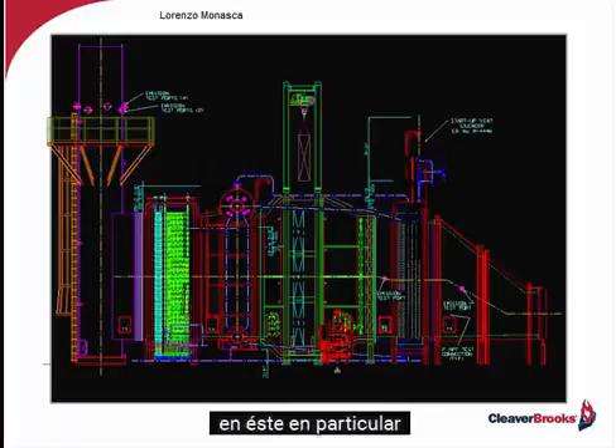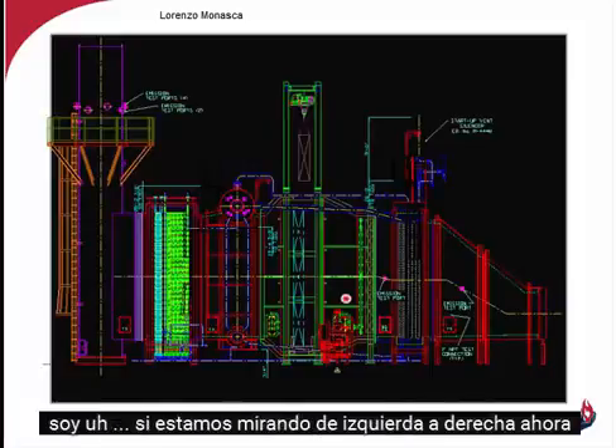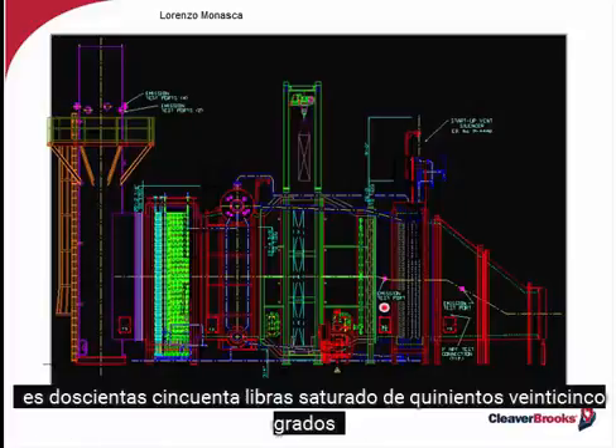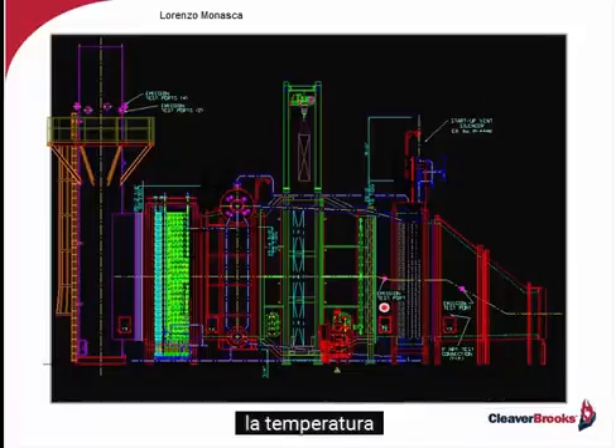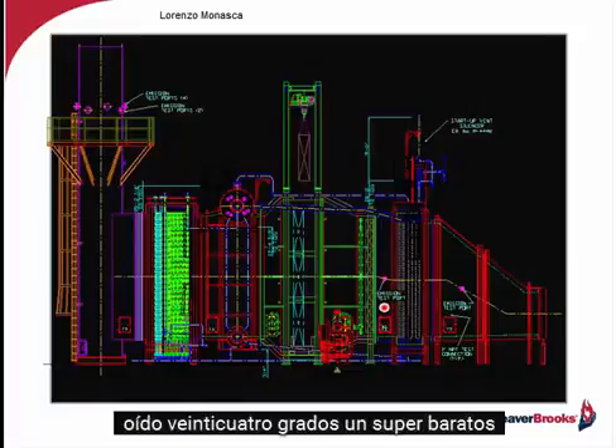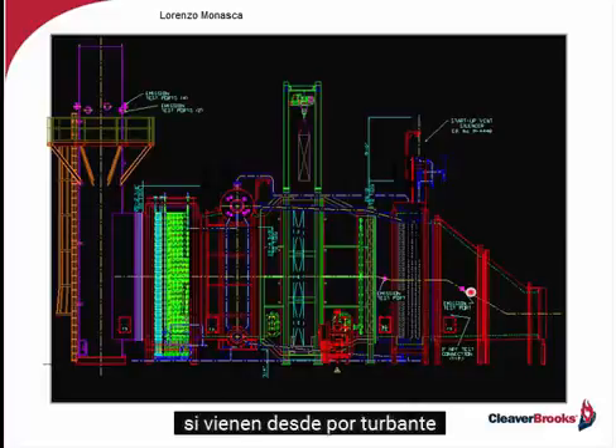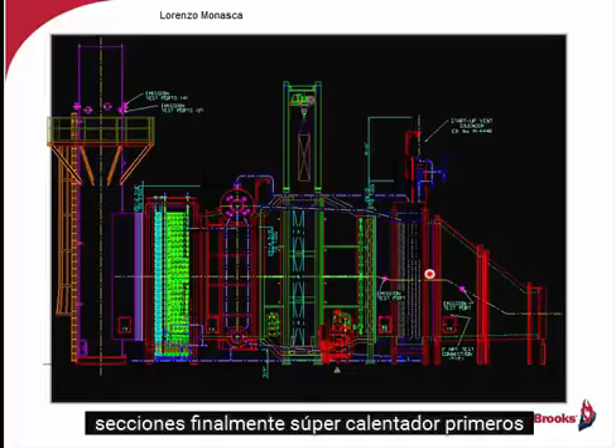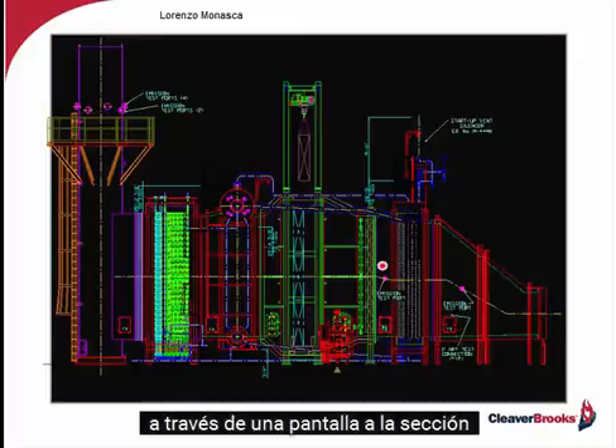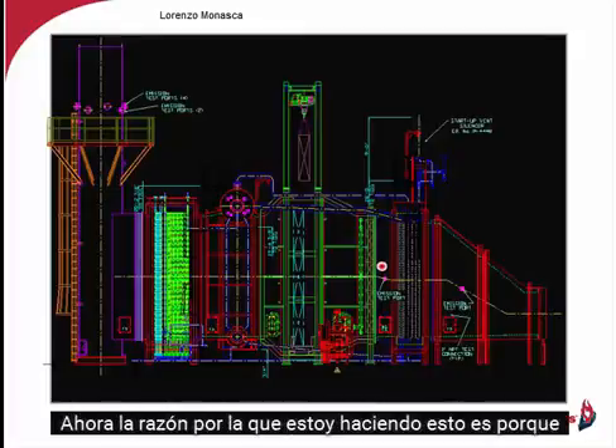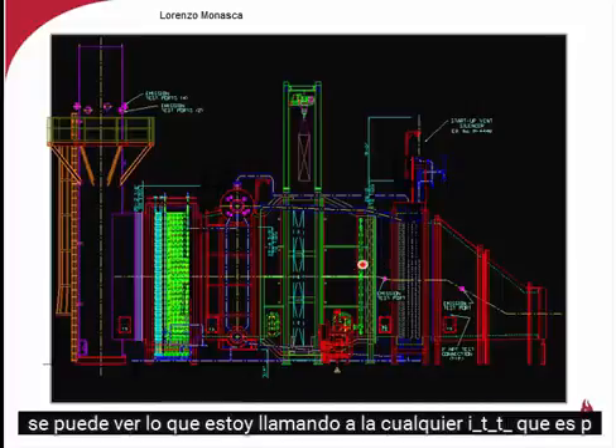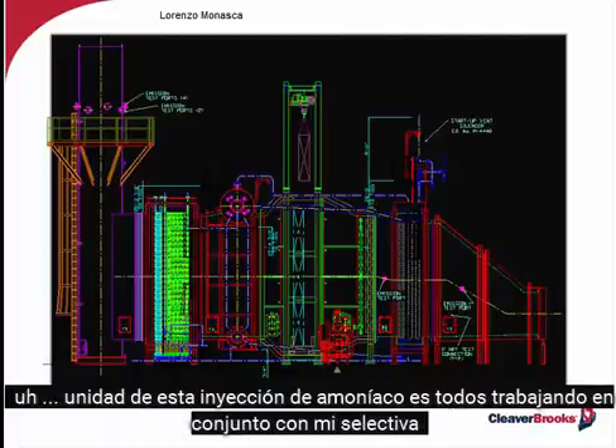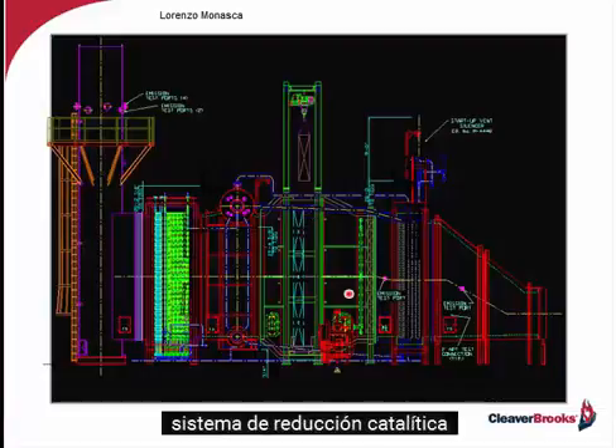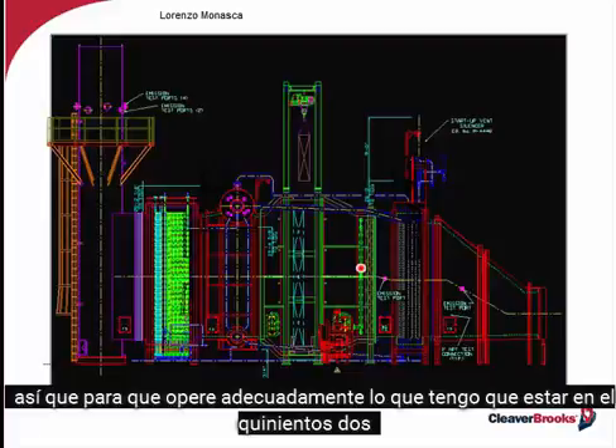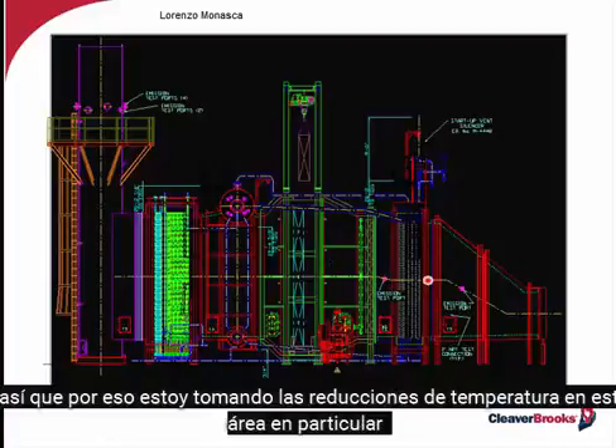Now, here's another example. In this particular one, if we're looking from left to right, it's 250 pounds saturated with 525 degrees temperature, 124 degrees of superheat. As I come in from my turbine, I come into the superheater section first. I then pass through a screen tube section. The reason I'm doing that is because as I get here, you can see what I'm calling the AIG, which is the ammonia injection unit. This is all working in conjunction with my selective catalytic reduction system. In order for that to operate properly, I've got to be in the 500 to 750 degree area for this catalyst to work properly. So that's why I'm taking the temperature reductions in this particular area.